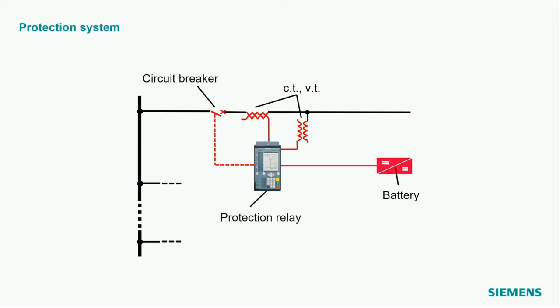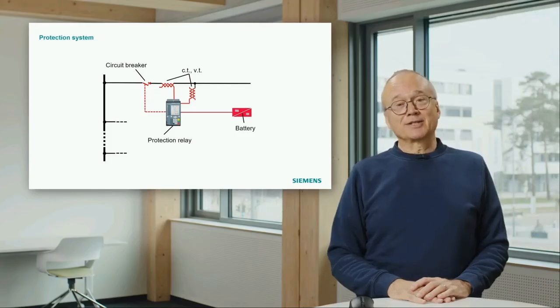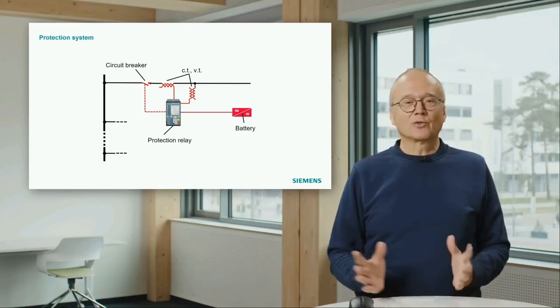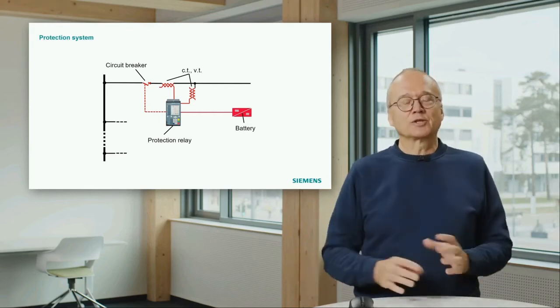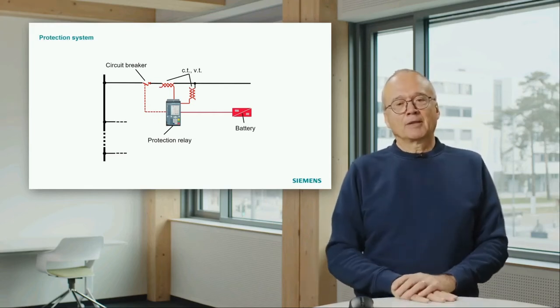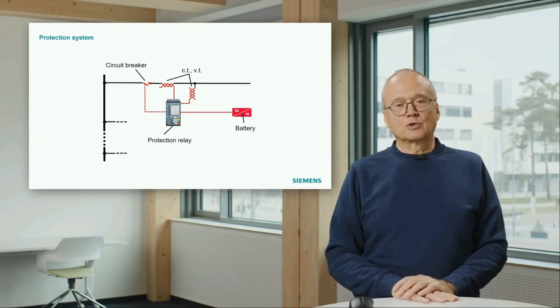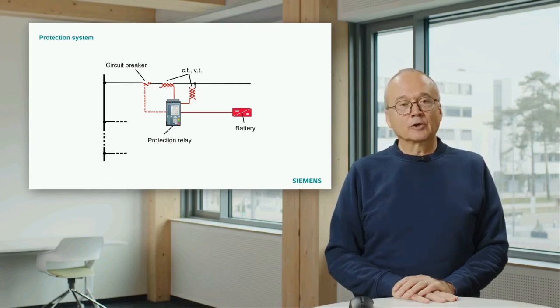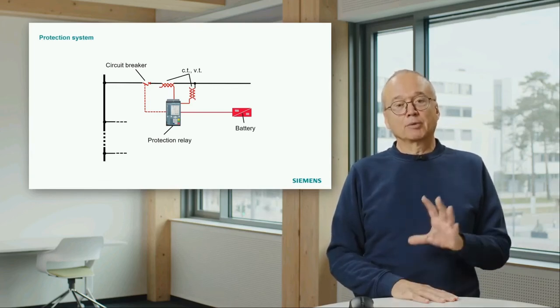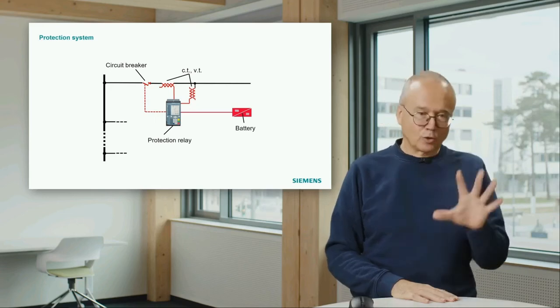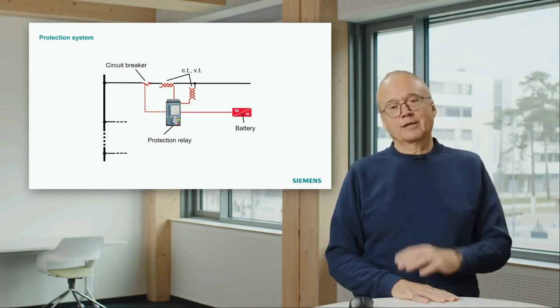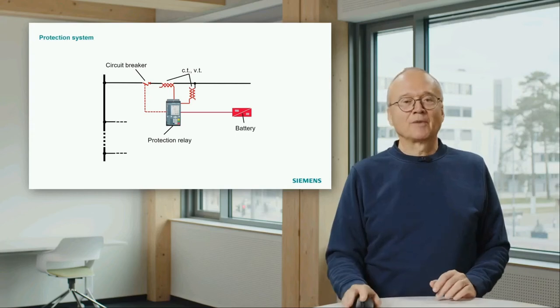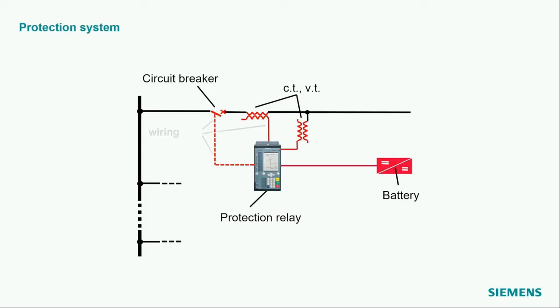We typically also use a battery in a substation. It sounds a bit strange to have a battery in a substation which is full of power, but that battery is used to give a reliable supply both for the circuit breaker, for the whole control system, and also for the protection relay. And what is also indicated here is the wiring.